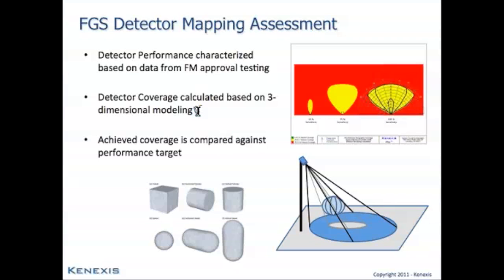As the detector is elevated away from the elevation of interest and the angle of declination increases, or the detector is pointed down towards the floor, the shape of the cone of vision dramatically changes. No longer do you get a sharp 45-degree angle cone of vision, and instead you get something that ends up looking a little bit more elliptical until the angle of declination is such that the detector is pointed straight down, at which point in time, depending on the make and model of the optical fire detector, you will have a circular cone of vision.